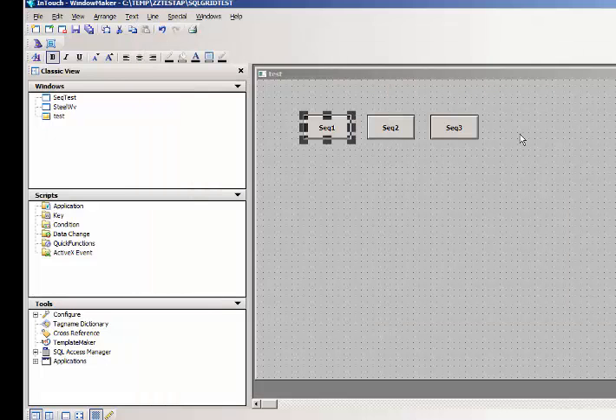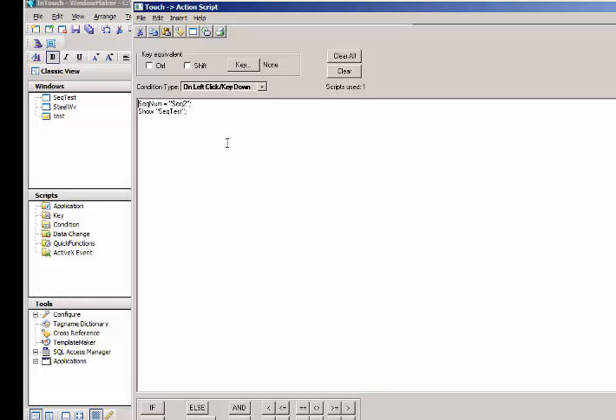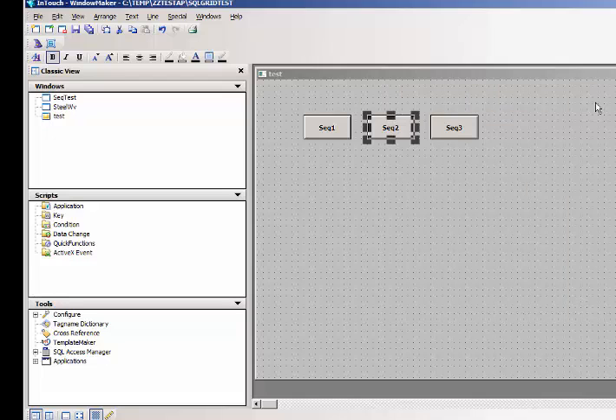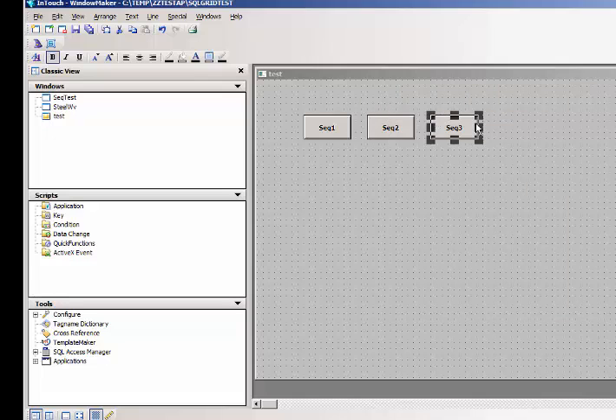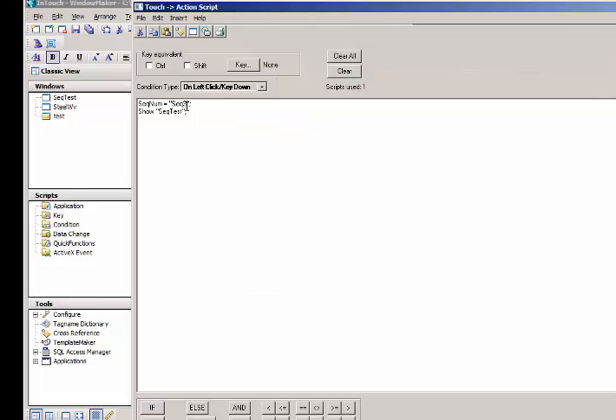If I look at sequence number 2 it's basically going to set that variable, same variable, sequence number to sequence 2 and then call the same faceplate. So same thing for number 3. So I'm just passing in the name of the sequence number to this variable, sequence number, so when I open up my faceplate it's going to use that to determine, set my IO references to point to the correct tags in the PLC.